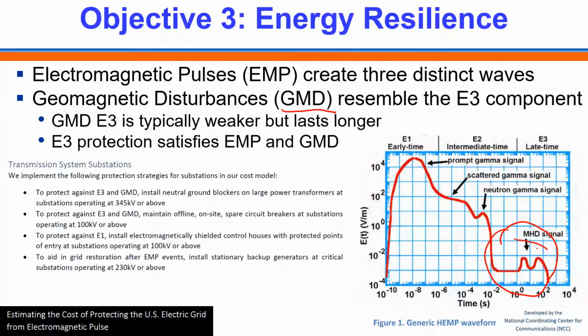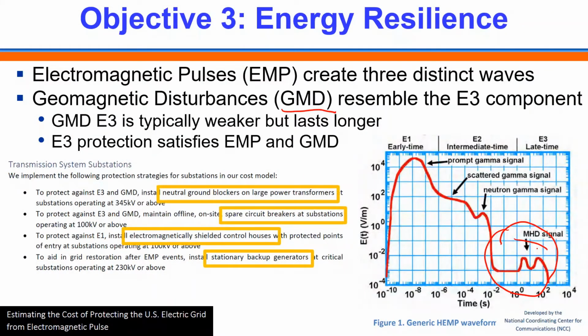There's a lot of guidelines for how substations and such can be protected from it. For protecting from E3, you would install neutral ground blockers on large power transformers. For E3 GMD, have spare circuit breakers at the substations. For E1, use electromagnetically shielded control houses. And for grid restoration after EMP events, have backup generators.